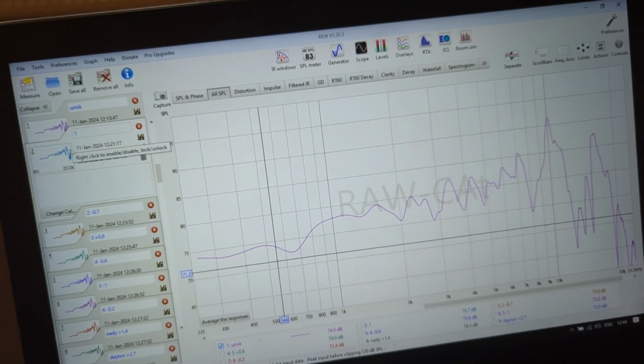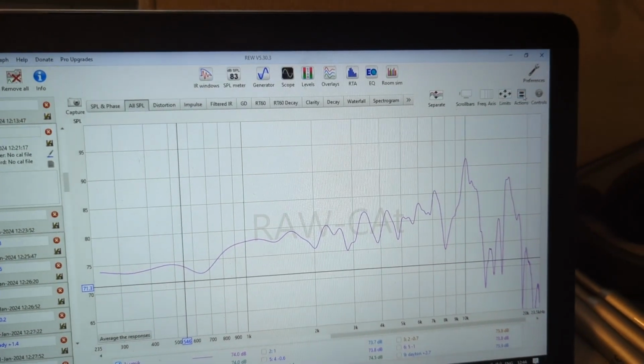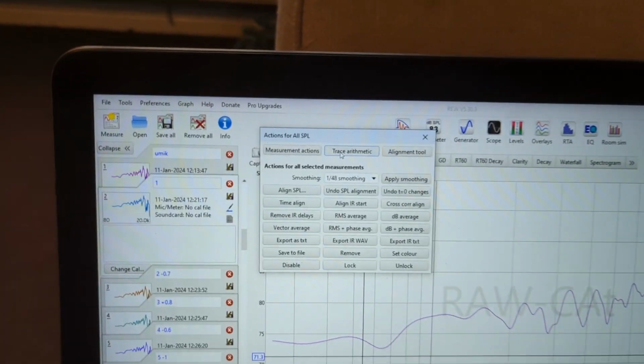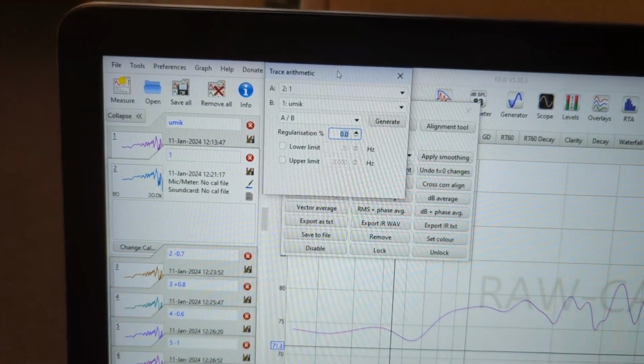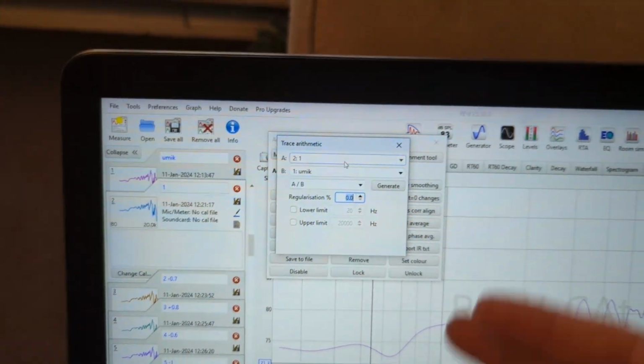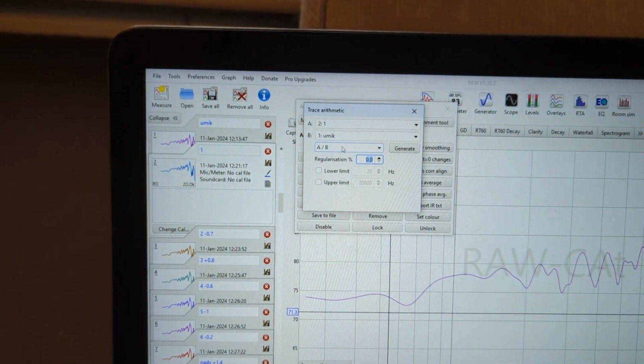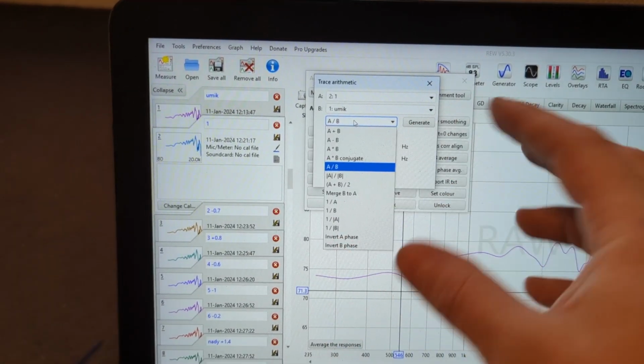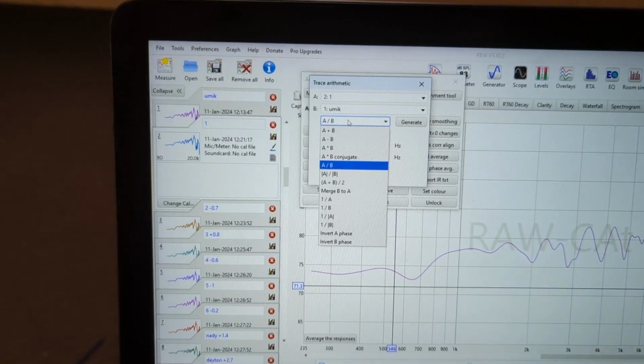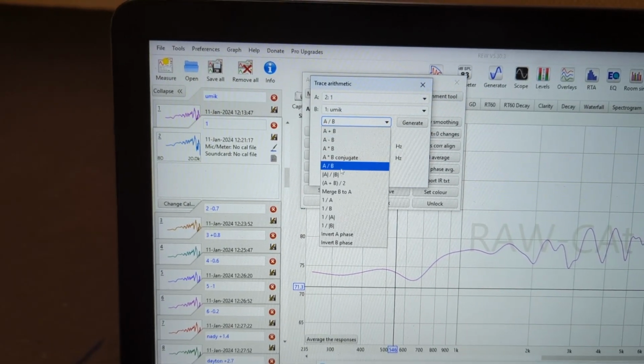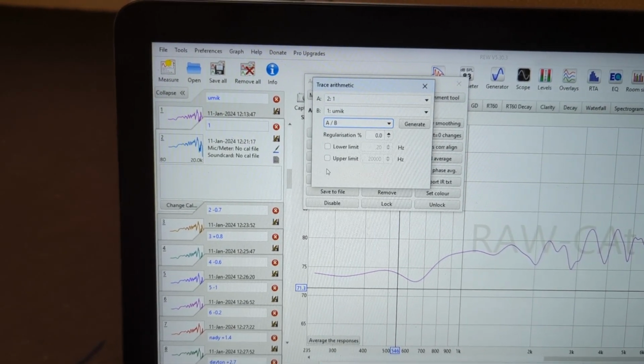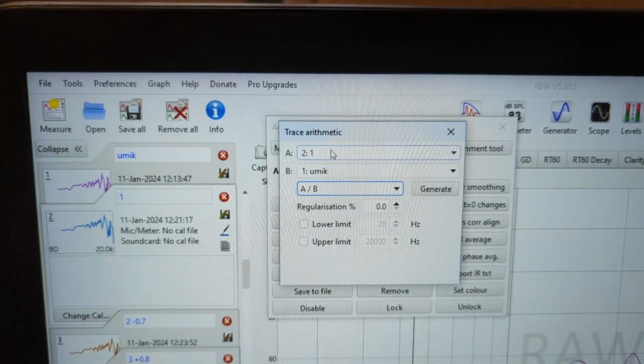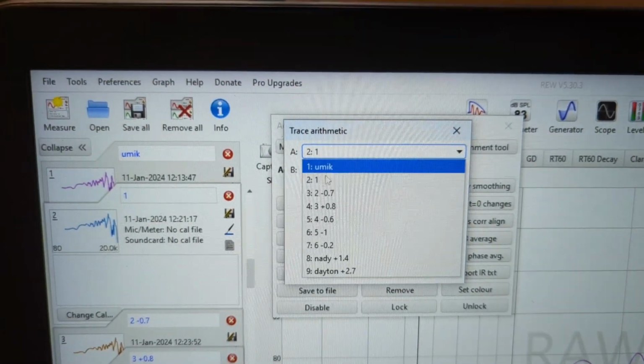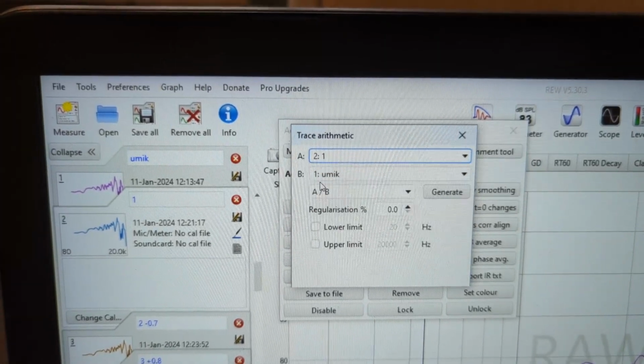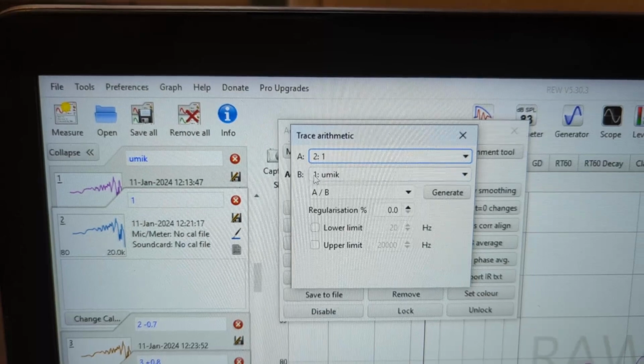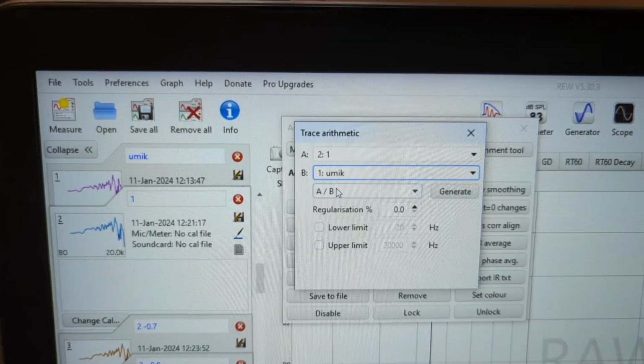So what I'm going to do is go to Actions and Trace Arithmetic. This basically lets me do some math between the measurements. You can do subtraction, division, multiplication, whatever you want. For this specific one, we need to choose A divided by B. A is going to be the microphone that I want to calibrate, in this case number 1, and B is going to be my reference, which is UMIC.